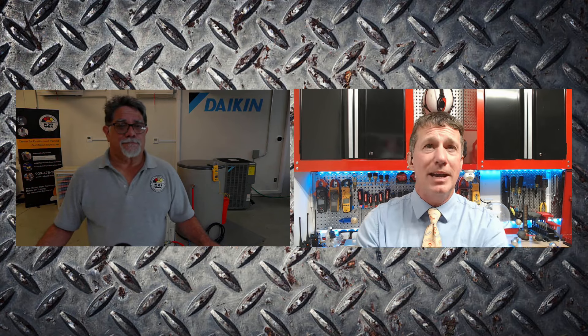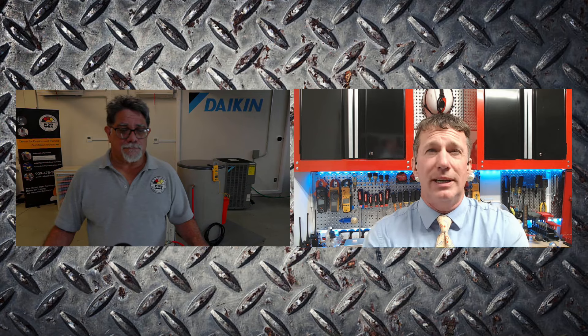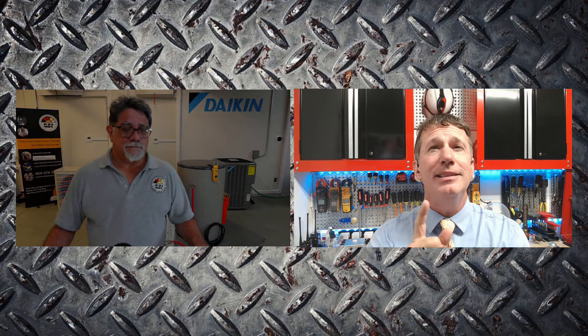The hybrid water heaters using heat pump technology use refrigeration cycles for producing heat as well as electric resistive heating elements — a combination, making them a hybrid system. But today's topic is a standalone heating system that is inverter-driven. It's not necessarily a heat pump because we're only operating in one cycle — the heating cycle — but it is completely refrigeration, running on CO2, which is truly intriguing. Today we're talking about CO2 water heating systems that are inverter driven.